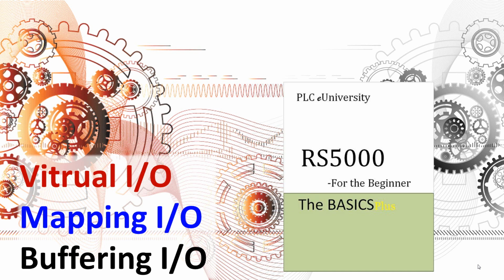and make it look like they are contiguous I/O points. And then of course buffering I/O is very important for the Logix engine, simply because with ControlLogix and CompactLogix, and as a matter of fact all of the RS Logix 5000 family, the I/O is not updated synchronously with the program scan. Whereas with, we'll call it the 500 arena, which would be SLC 500s and MicroLogix, they could not chew gum and walk at the same time.